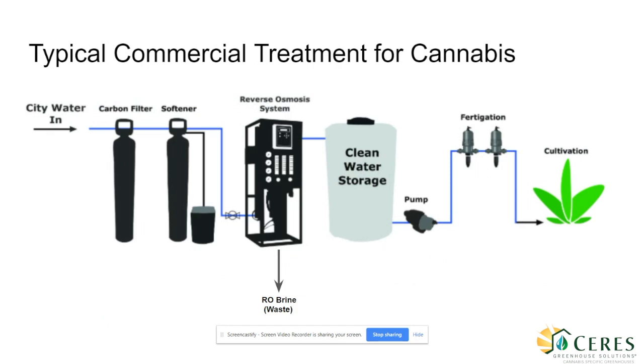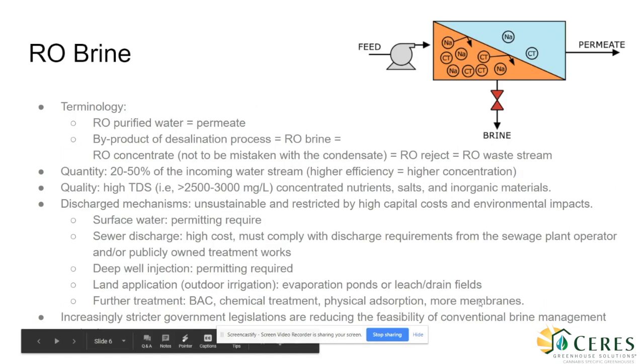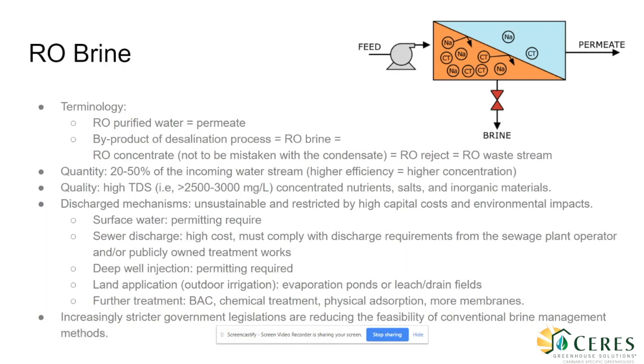Here's a sample of what you'll commonly find for a water treatment system in a commercial cannabis facility. Incoming water will go through some sort of sand or carbon filter, water softening to reduce the hardness, and RO to remove all other constituents for storage. The purified water will then be dosed with nutrients according to the specific grow recipes before going to cultivation. You'll notice in this diagram there is an RO waste stream coming out of the RO system. This is one of the major drawbacks of the RO system. RO purified water, often called the permeate, is the product of the desalination process. The byproduct is the brine, also called concentrate reject water or waste stream. This waste stream can be up to 50% of the incoming stream, so RO systems are not water efficient.